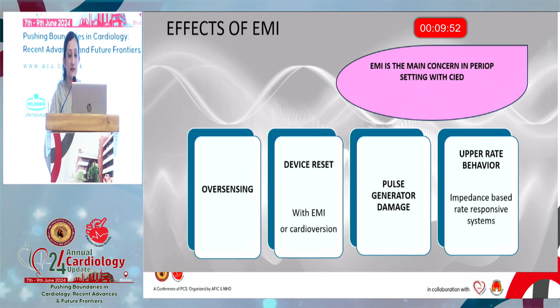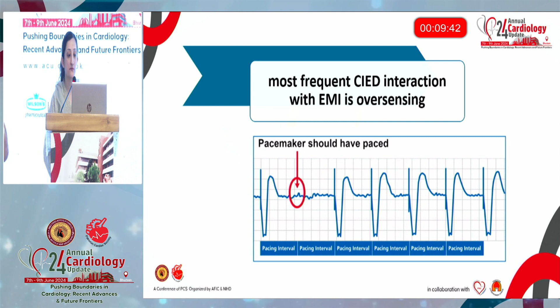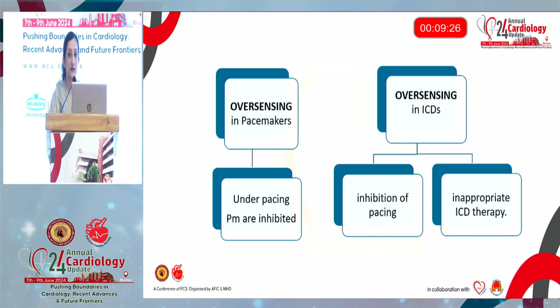It can cause problems of oversensing, resetting of device to factory settings, permanent damage to the pulse generator, and upper rate behavior. The most frequent interaction of the devices with electromagnetic interference is that of oversensing. The oversensing can lead to underpacing. The underpacing can lead to pacemaker inhibition in case of pacemakers. Apart from inhibiting pacing in ICDs, it can also lead to inappropriate detection of tachyarrhythmias with inappropriate ICD shock deliveries and ATPs.